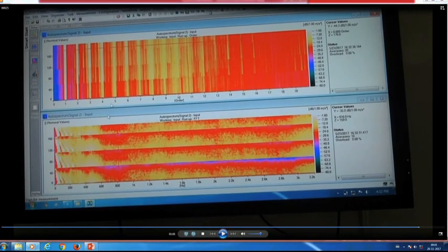So, you see here the top one is the order analysis plot and the bottom one is the normal FFT plot, and this is the spectrogram, that means the colored FFTs projected into the plane as a color contour. You see there is a lot of frequency smearing, and this is still 3.2 kilohertz, and these are the 4 times we have increased and decreased the speed of that rig. But if you look at the order plots, you will see that the distinct orders which are related to the rotational speed strictly come out as straight lines. So, this is a strong presence of rotational orders in such a system.